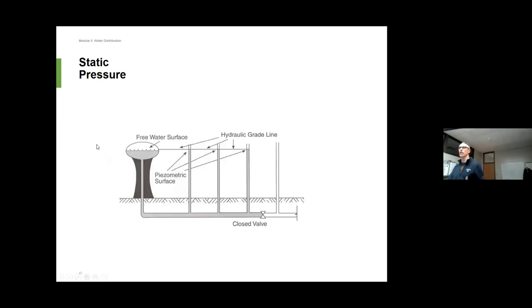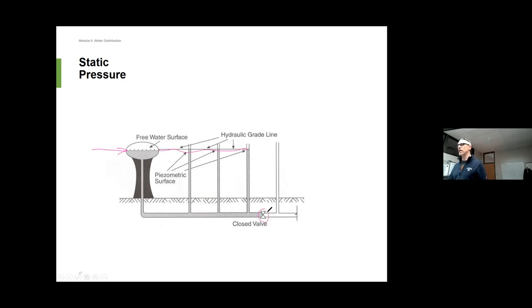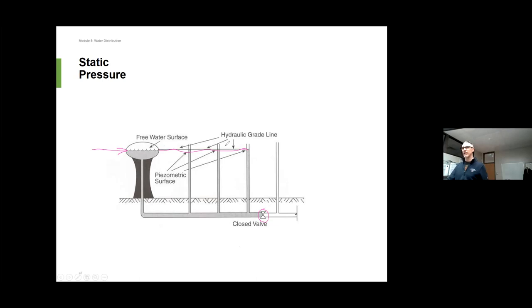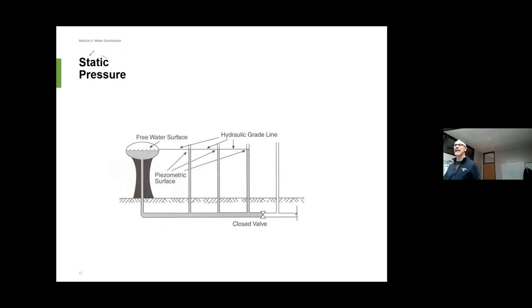Pressure is what moves water all over the place. In this photo, the level in this reservoir is going to dictate the pressure across the system. If I have my valve closed and no water is moving, that's called static pressure — it's equal to the level in the storage tank. If I have houses here, here, and here, all three of those houses are going to have the same pressure right now because no water is moving. They're all hydraulically equal. The line across here is called the hydraulic grade line, which is equal to the level in the reservoir when it's static.